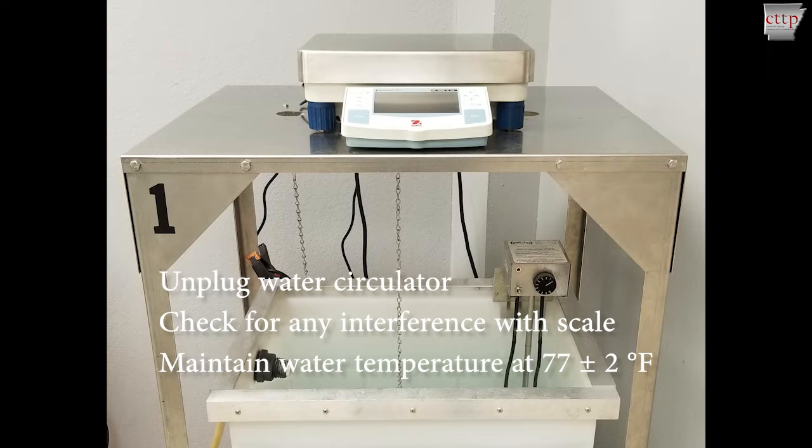Unplug the water circulator in the water bath and check for any interference with the scale, both above the platform and below. Maintain the water bath temperature at 77 degrees Fahrenheit.